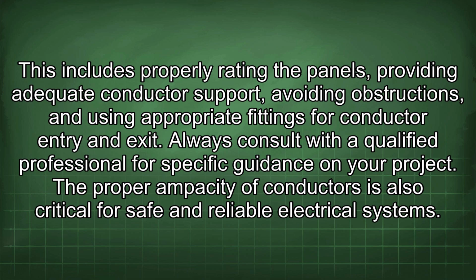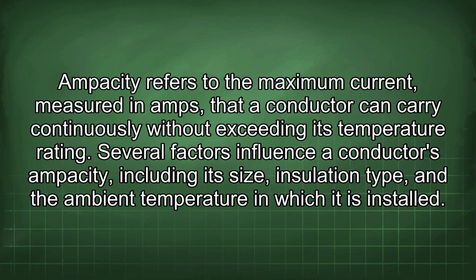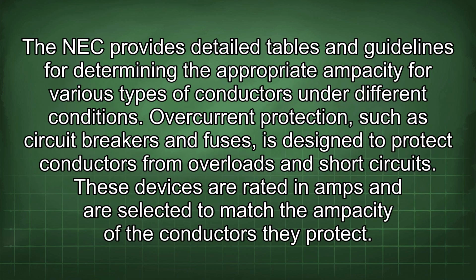The proper ampacity of conductors is also critical for safe and reliable electrical systems. Ampacity refers to the maximum current, measured in amps, that a conductor can carry continuously without exceeding its temperature rating. Several factors influence a conductor's ampacity, including its size, insulation type, and the ambient temperature in which it is installed. The NEC provides detailed tables and guidelines for determining the appropriate ampacity for various types of conductors under different conditions.